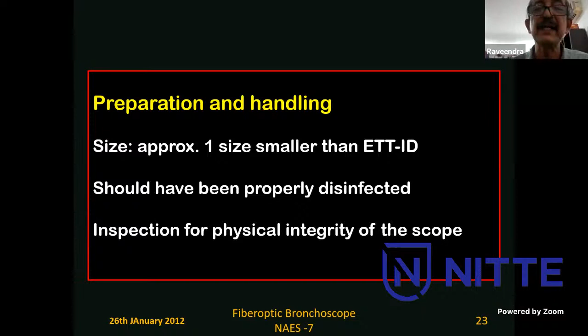If there is a leak, then we should not use it if it is badly leaking, because once you use it with a leak, it can worsen. It's like a vicious cycle. It can worsen very easily, and repair can be very expensive. And unfortunately, I do not have the picture. You can see on the monitor all the dark spots, black spots. If it is damaged, it's very easy to identify.